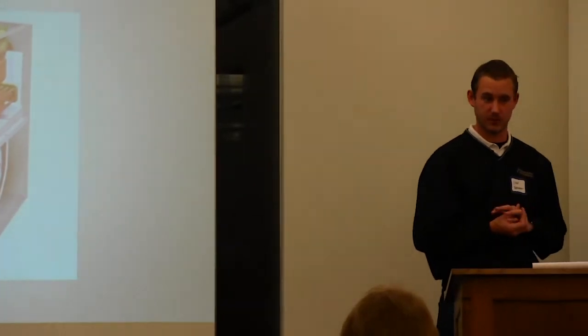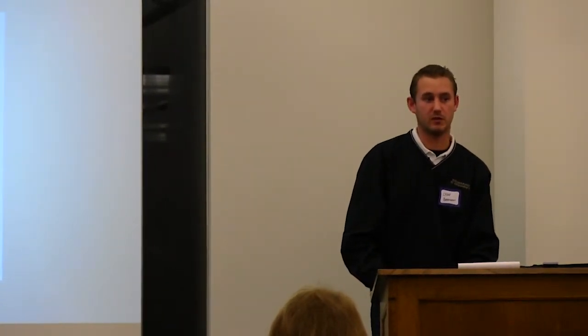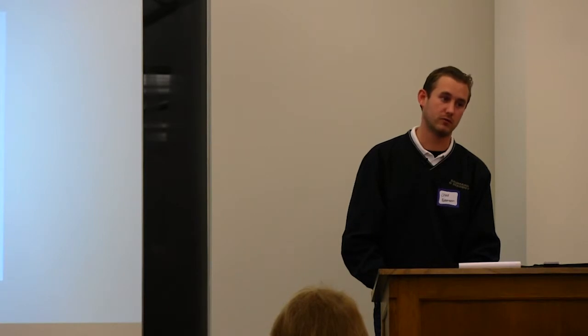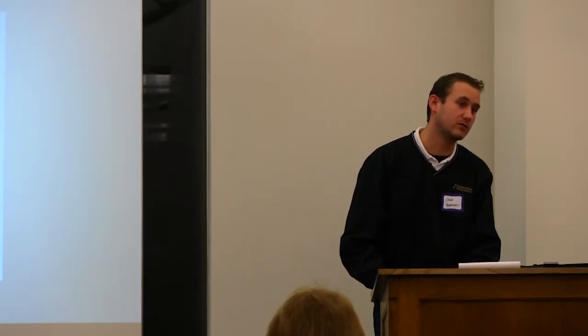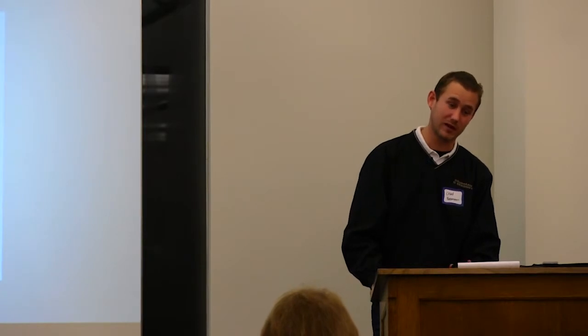And everybody except for Trane and Lennox has just a real nice, easy way to track that. And so if your furnace is not a Trane or a Lennox, generally the first 4 numbers indicate the week and the year that it was manufactured. So it would be like 4214, so the 42nd week of 2014. So that would be an easy way to track that down. But if you have a Trane or a Lennox, unfortunately, you'll have to go online, because they have it in a code, and that code changes from model to model. It's infuriating.